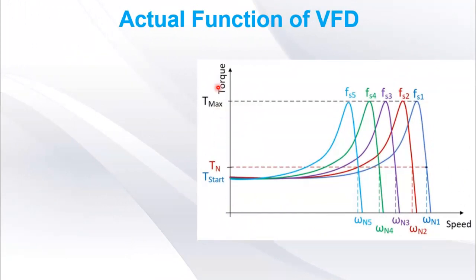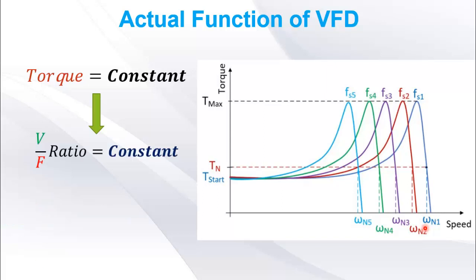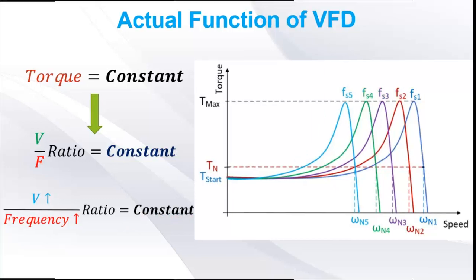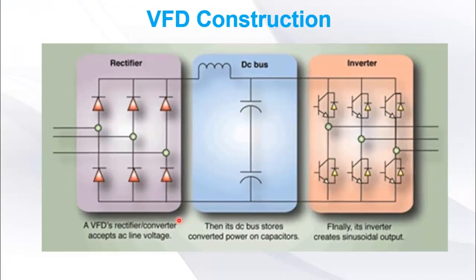Here we can see constant torque can be generated at different speeds by keeping V over F ratio constant. In other words, in order to increase the speed, we have to increase the frequency and supply voltage at the same time to keep V by F ratio constant. And this is the main function of variable frequency drive.